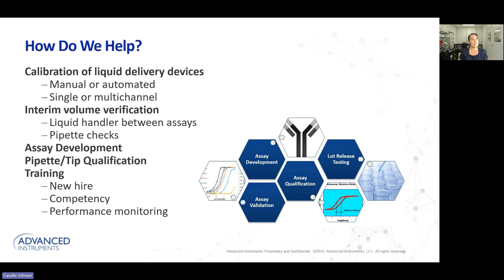And so when we think about our systems, again, we've got a couple of different systems. The MVS system is pictured over on the far left. Again, that's really designed for multi-channel pipettes and automated liquid handlers. But we also have the PCS system. Again, that's what we're here to see today, depicted over on the far right-hand side. So the PCS system is used to calibrate volumes down to 0.1 microliters up to 5,000 microliters. So a pretty broad range of volumes that you can test.